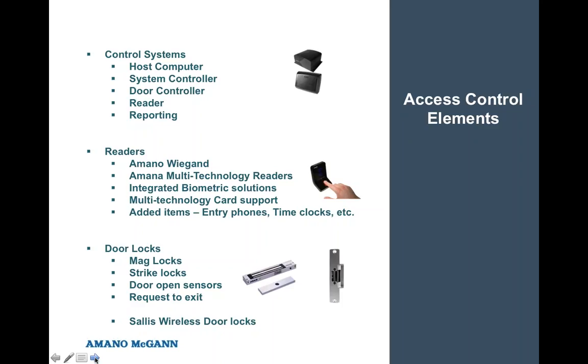And maglocks and door strikes, if you look at how we actually secure those doors, it's dependent on how secure you want the doors. Maglocks are typically used in a facility when you want access to be denied for both or allowed for both sides of the door. So in the memory care, for example, we typically put maglocks because we want access to be recognized on who is going in and who is going out at all times. So it's kind of like a track record as well. It's your reporting structure, telling you who's been in that area and who's not been in the area, and to restrict that.